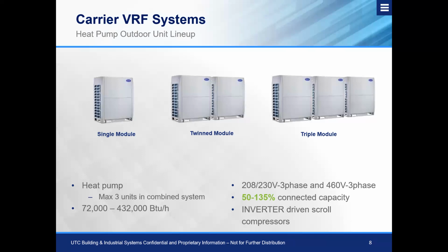Now, the heat pumps, just like the heat recovery, are available in a 208/230 volt 3-phase and 460 volt 3-phase application, and will range from a 50% to a 135% connected capacity ratio. So when we talk about differences between the heat pump and the heat recovery side, we have a little bit less connected capacity ratio than we do on the heat recovery, which was 150, unlike the heat pump, which is 135. And then, of course, just like the heat recovery option, we're still using our inverter-driven scroll compressors.